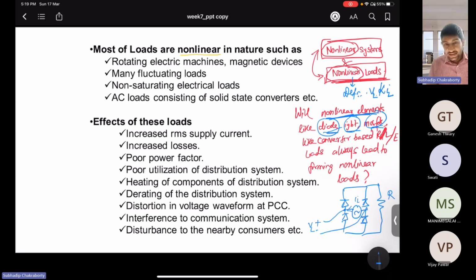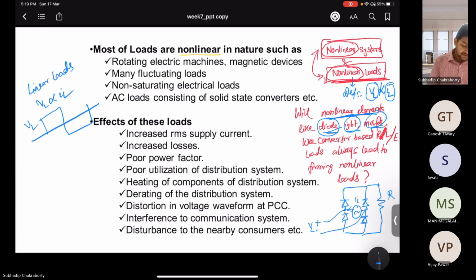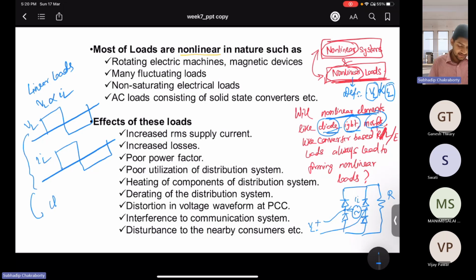And one more thing. Don't get confused by the term linear loads, that this VL and IL need to be always sinusoidal. Linear loads mean VL should always be proportional to IL. Now someone tells you this is a square wave. This is VL, IL is also like this, not sinusoidal but square wave. Is this an example of a linear load? Answer is yes. They may have harmonically distorted voltages and currents going through them or impressed across them, but the nature of that load can be classified as a linear load.